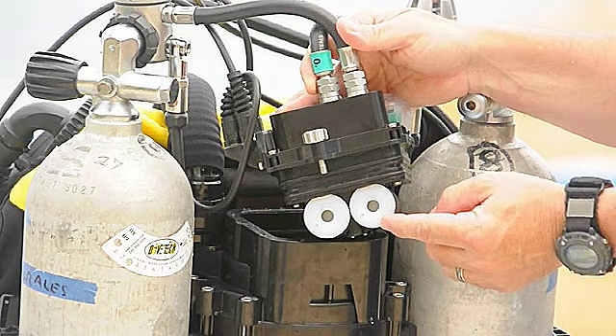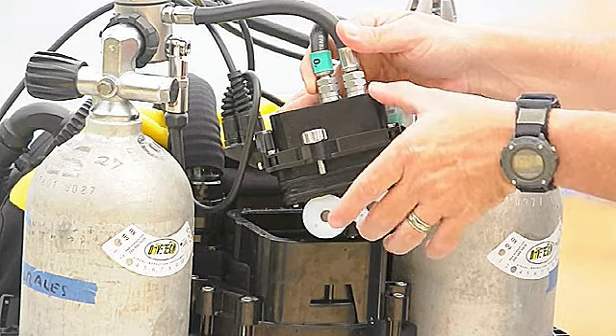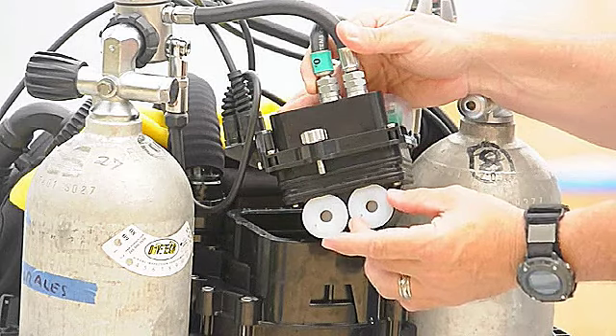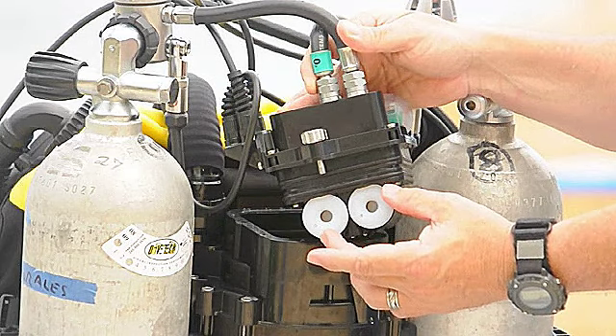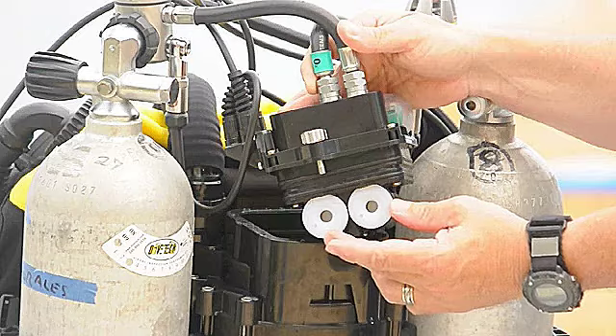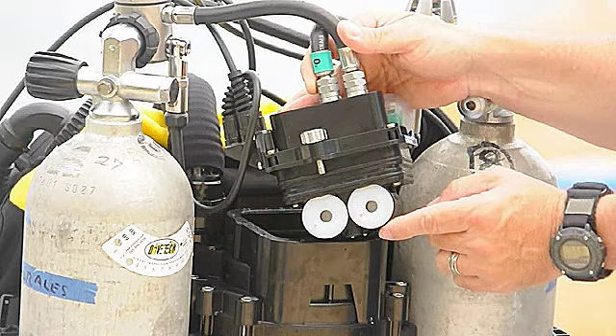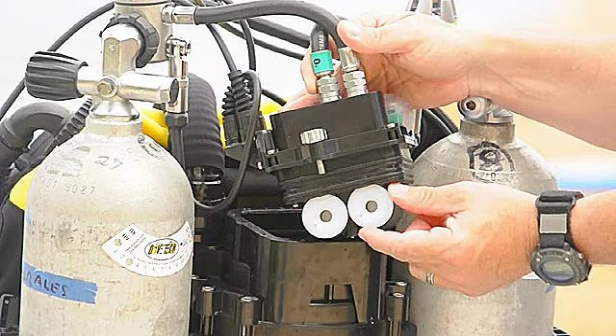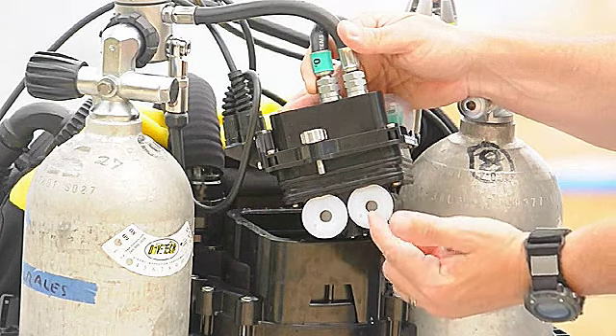And as an added bonus, once you've got this system in place where you've got this module here connected straight into the oxygen sensor chamber, you can also do automatic calibration. It'll calibrate the oxygen sensors automatically every time you power up the system, and it only requires a small amount of gas to do that.